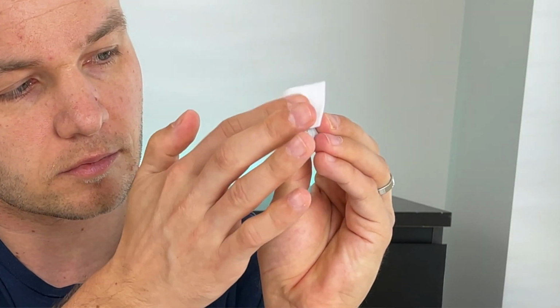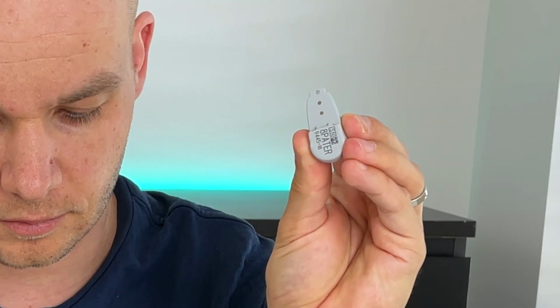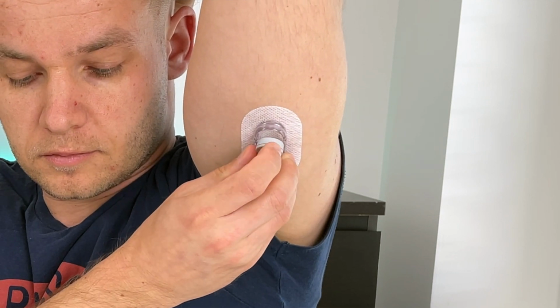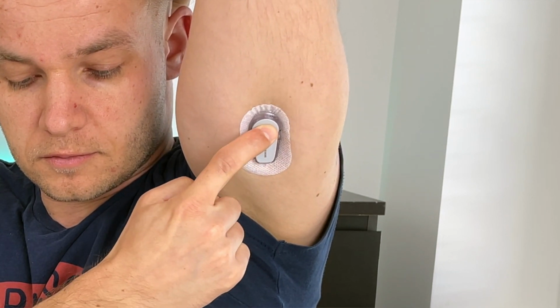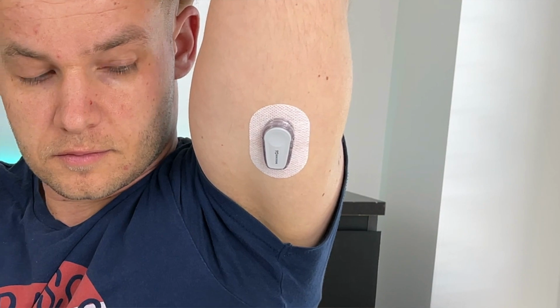We need to attach the transmitter. Take the transmitter, clean it with an alcohol wipe and let it dry. Then insert the toe of the transmitter into the slot of the transmitter holder and snap the transmitter firmly into place. The transmitter is good for 3 months and you can use it repeatedly for a total of 9 sensors.